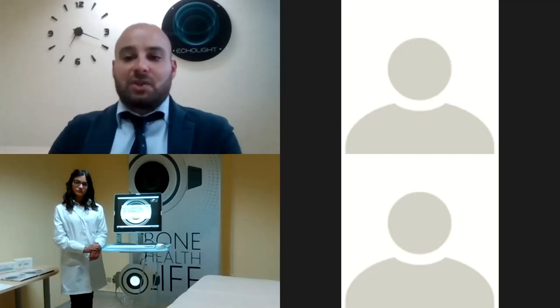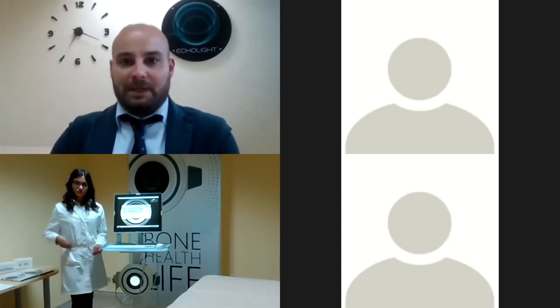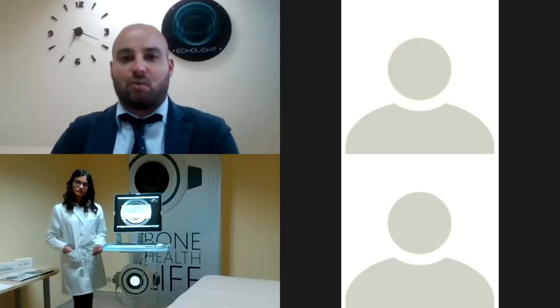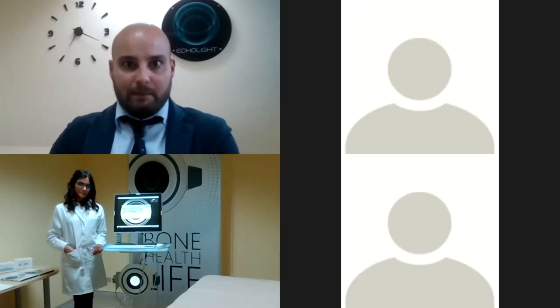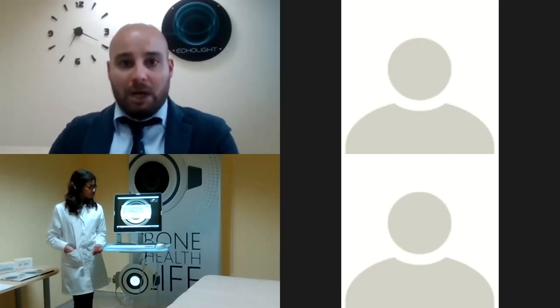Aorta calcification. Well, actually, one of the many advantages of R.E.M.S. technology is the automatic exclusion of possible aorta calcifications. Why? Because the system will automatically detect the interface of the vertebra and then perform the analysis on the region of interest, which is below the vertebra. So in case of calcified aorta, this is sort of transparent for our algorithm.